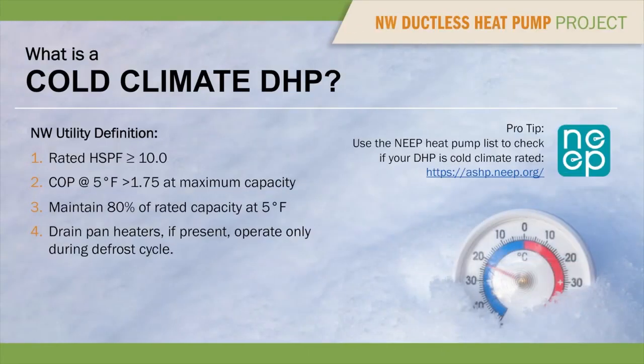Now, let's cover a working definition of a cold climate heat pump. Utility programs and state agencies across the USA have created the list of criteria you see on the screen. A cold climate heat pump must have an HSPF rating of 10 or more. This demonstrates that the unit is purpose-built to operate efficiently. COP, or Coefficient of Performance, is another energy efficiency rating, and it shows us how much energy it takes to produce a unit of heat.